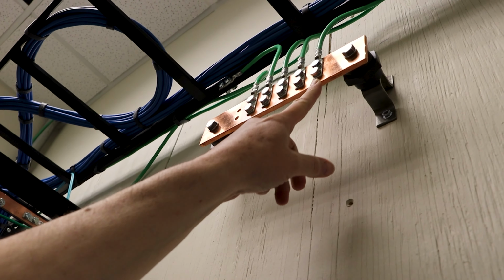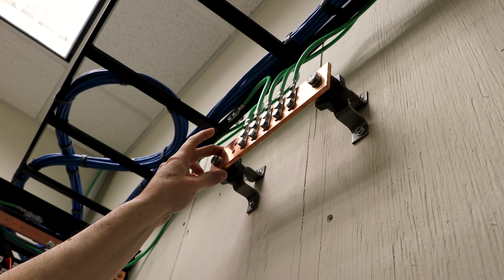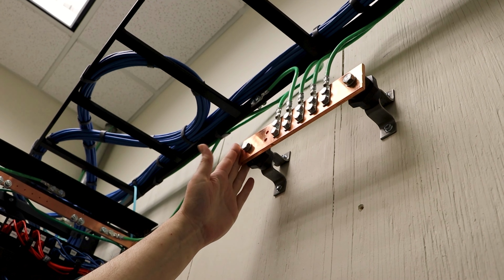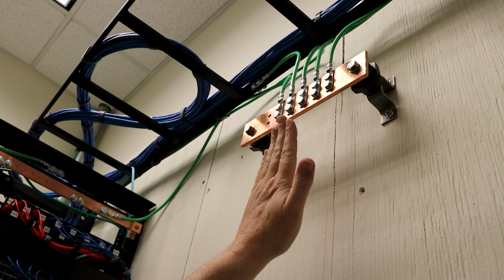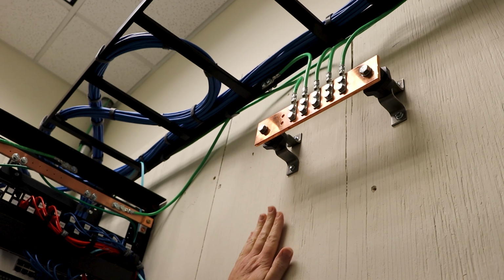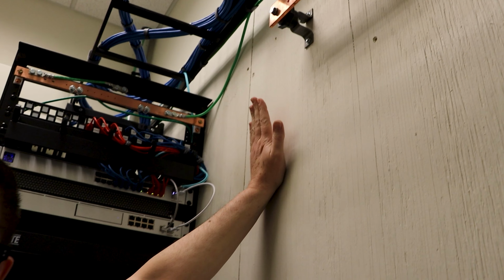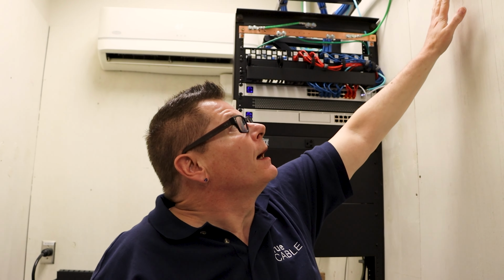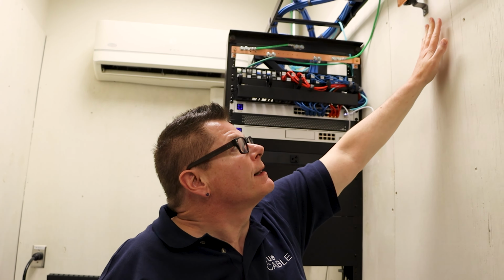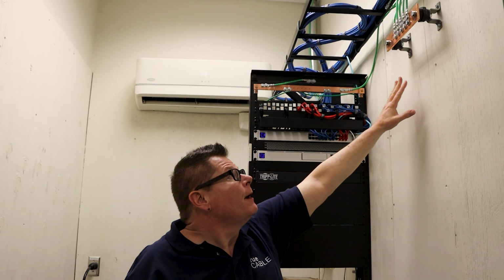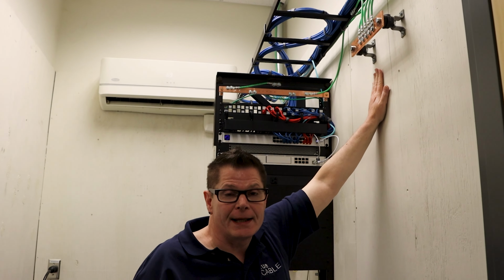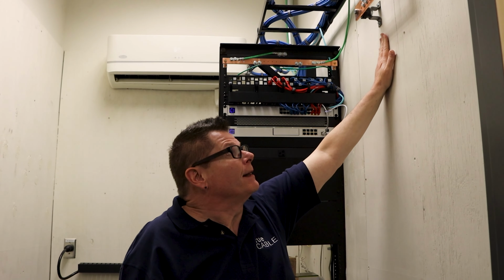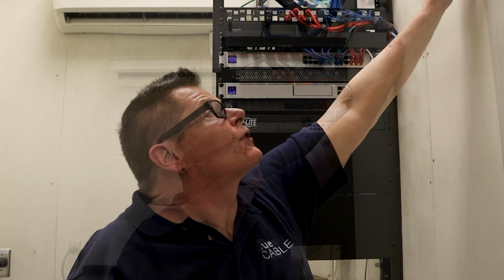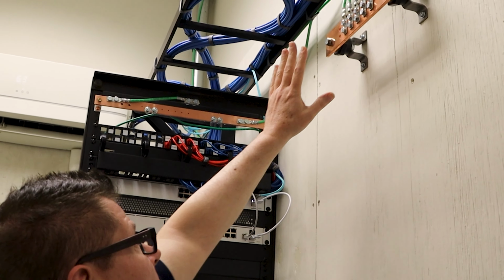And it's screwed down to a UL listed copper bus bar, and it has to be attached to plywood. The reason why this plywood is here, this is fire rated plywood with fire retardant paint, is because if something serious should occur, like a serious short or a lightning strike, an electrostatic discharge, then this is not nearly as apt to burn. And so that is part of fire safety. So we've gone and equalized everything in this room.